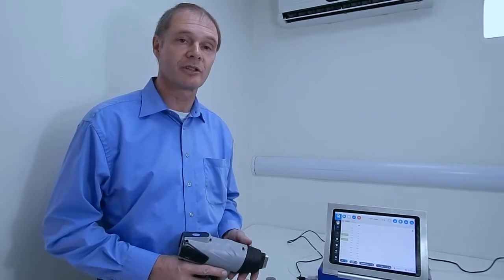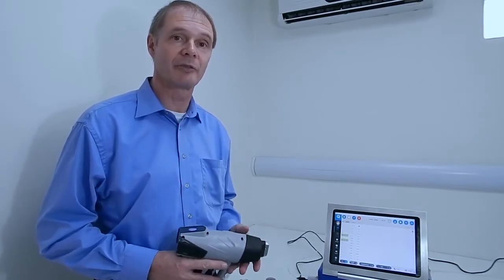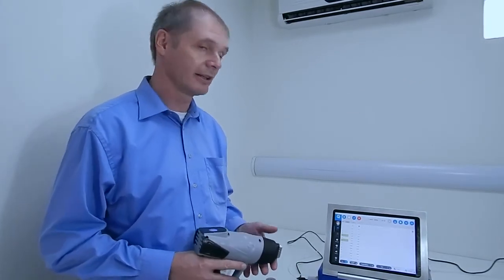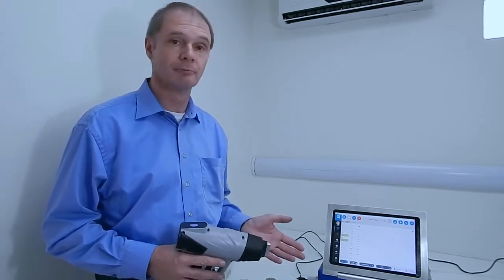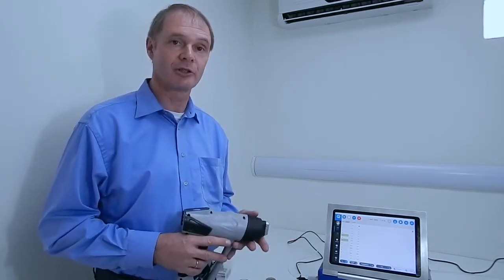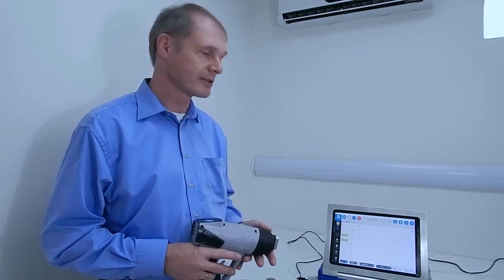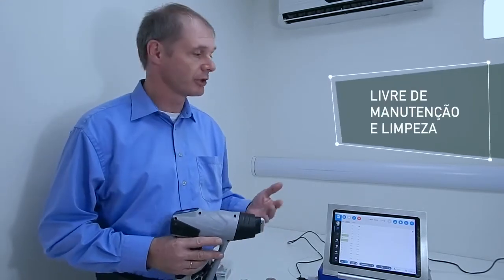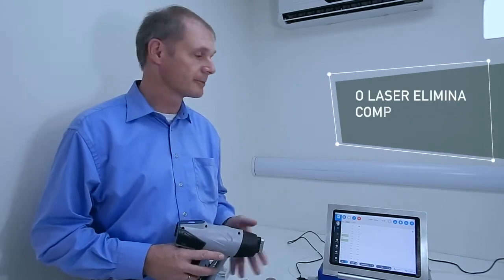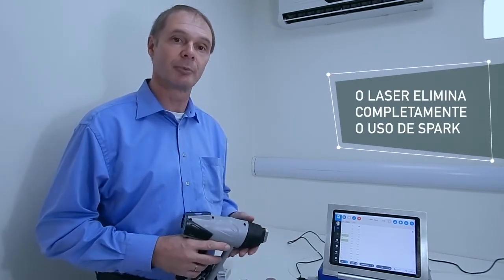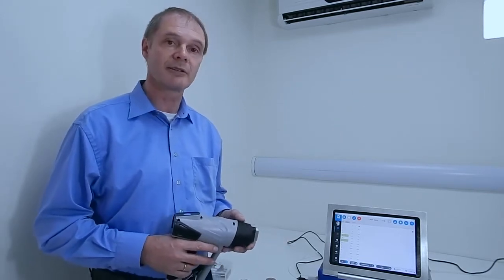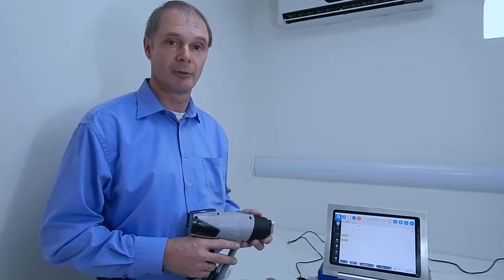One very important question is always, what about maintenance? How difficult is it to maintain the instrument? So we have good news for you. There is virtually no real maintenance with the instrument. We don't have an electrode, we don't generate a lot of condensate, there's no exhaust to be cleaned. So compared to a typical spark spectrometer, the time that you need to invest into maintenance is very close to zero.